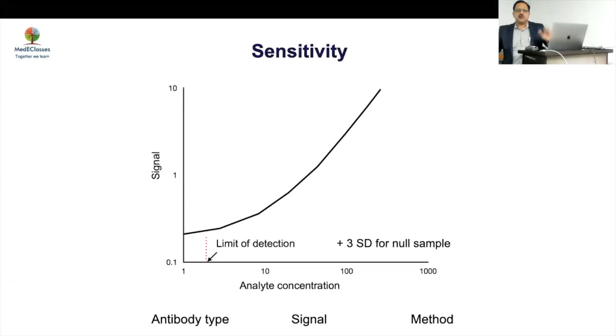If you have this much signal, you are seeing this depends upon how well you collect that signal. So if your sensitivity for the signal is good, you can measure any level. This is what happens. Now, what you're actually looking at is not limit of detection, you're looking at limit of quantification. That is the point at which you reliably measure your particular level. That is, your CV is less than 20%. So your limit of detection may be right up there, but you can have a CV of 80%, which is of no use. What you're looking at is a limit where the CV is 20%, which becomes important from that perspective.